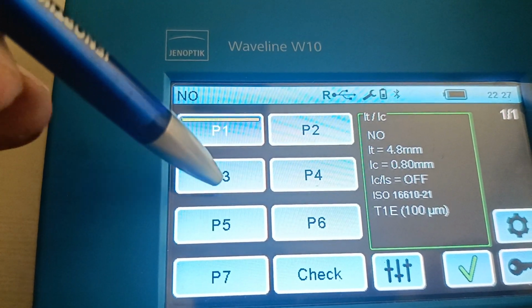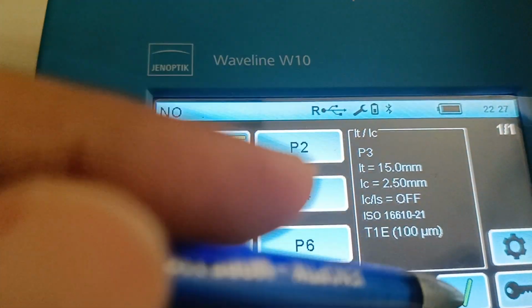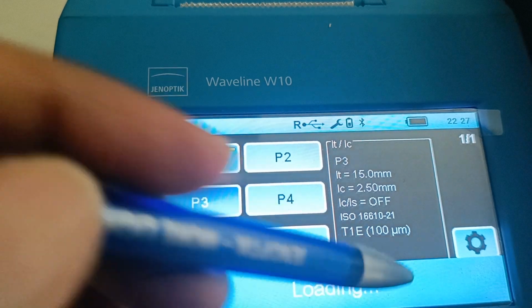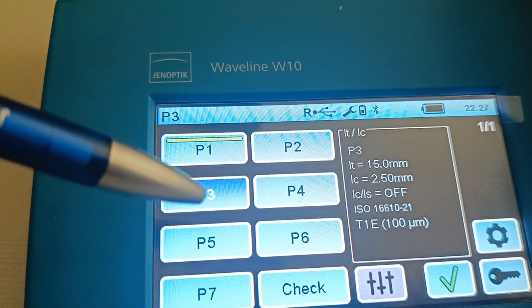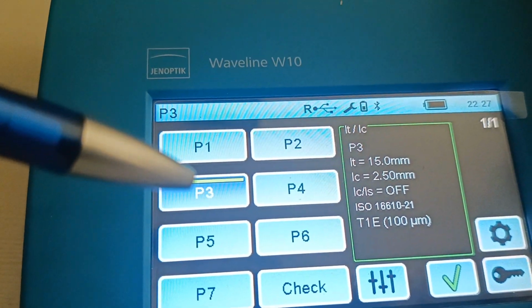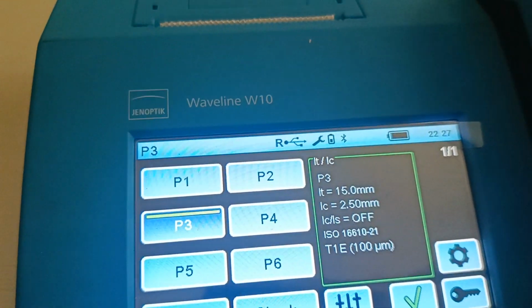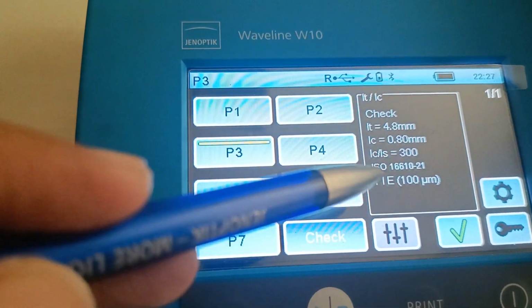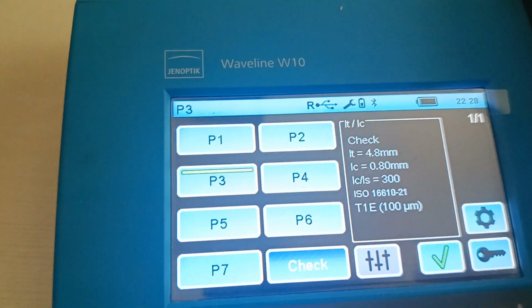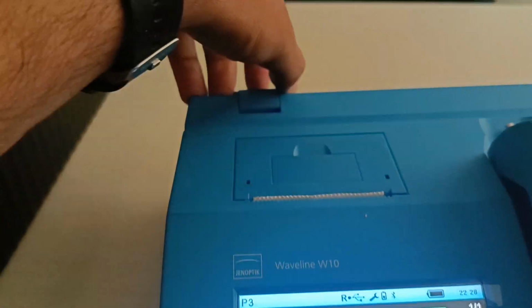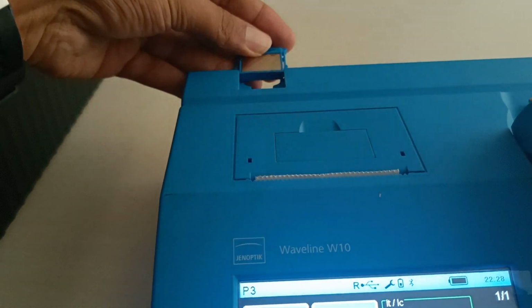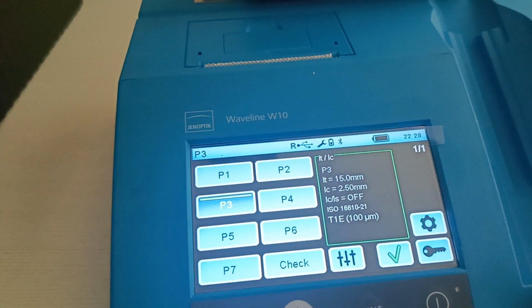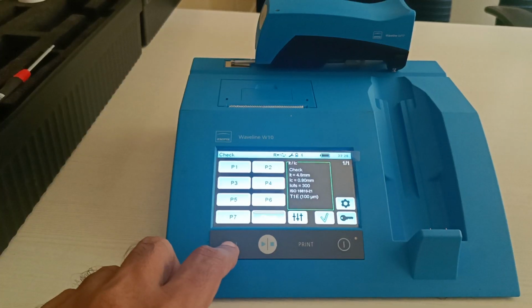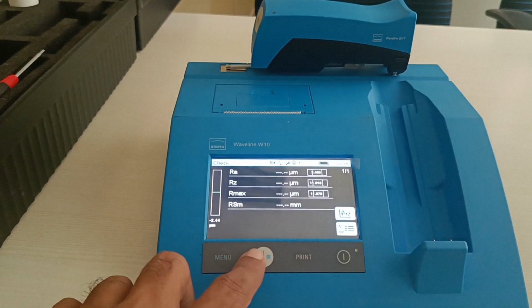So if you want to change it to P3, you have to select P3 and put this tick mark. So the green line will change to this program, and the measurement can be done according to this program. And this check is for the calibration data. So when we want to check with the master, we have a master here which is integrated to the system, and it is protected from environmental hazards. Now you can take the probe and just load it and you can check, so you will get the calibration data. So now you can press the menu and you can just press start.